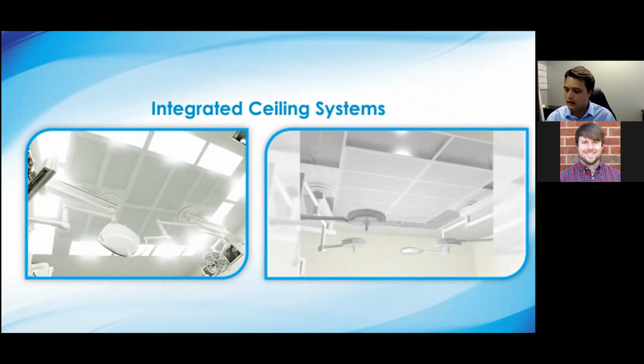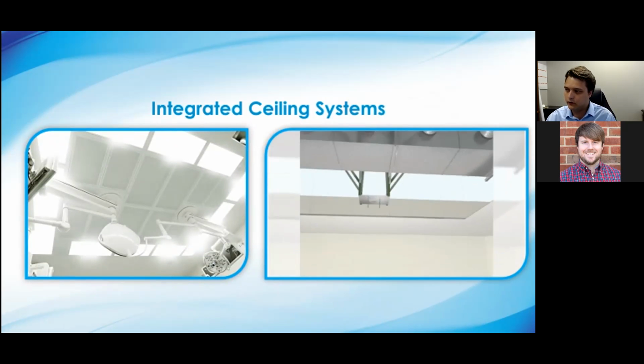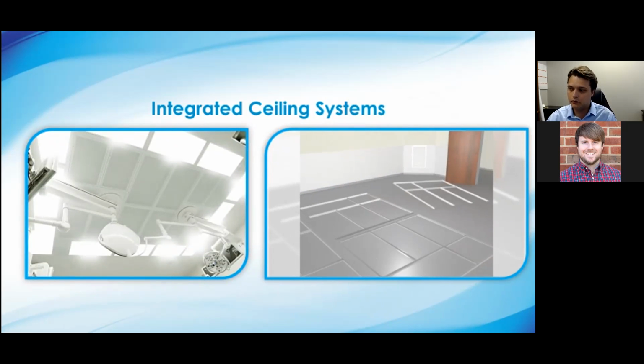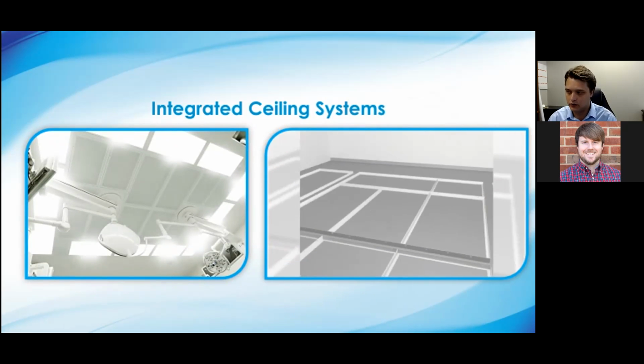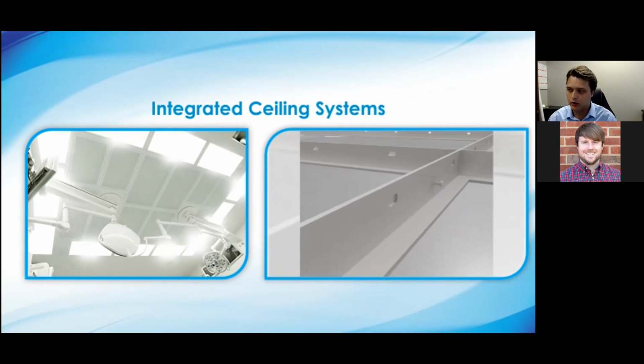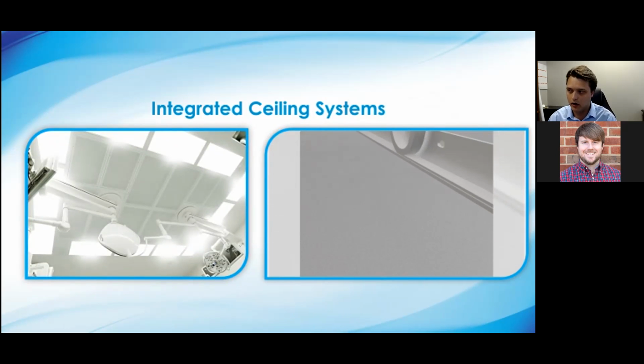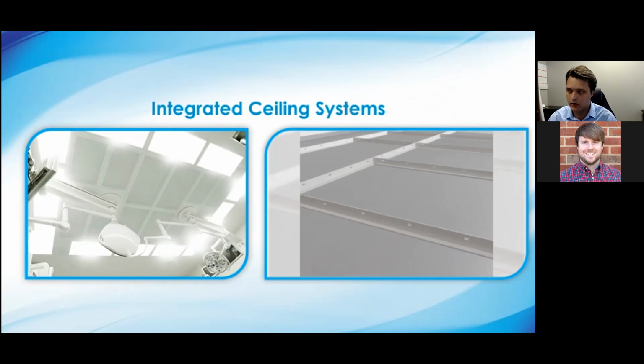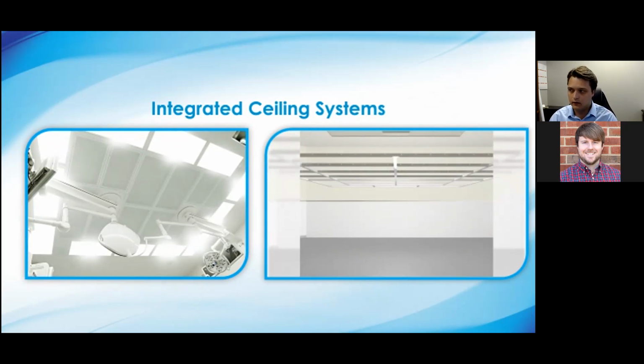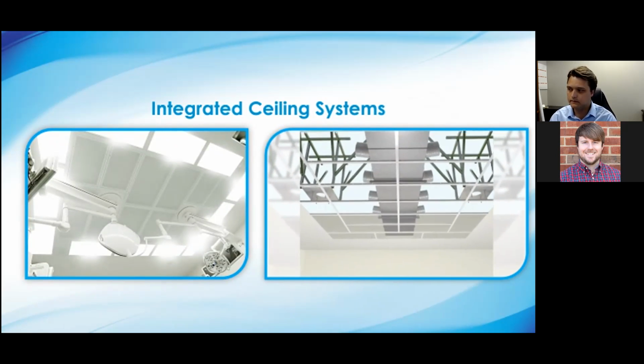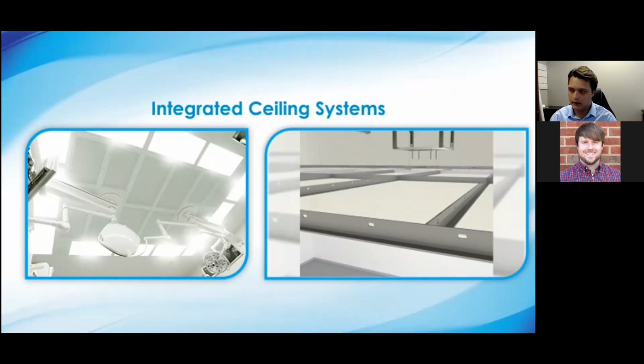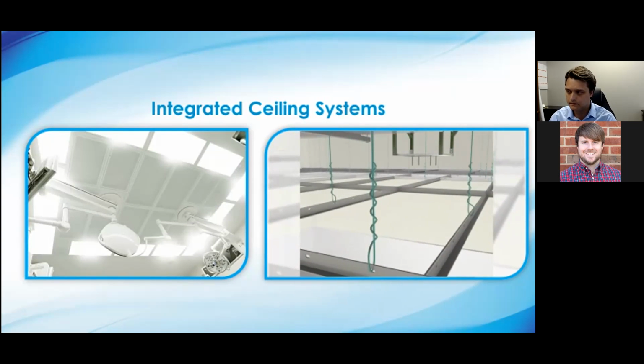Here we're going to look at an operating room under construction. We have one large ceiling opening. Those puzzle pieces, the modular framing sections, are prefabricated and pre-coordinated with all the openings and where everything is going to be within it. It's gasketed, fastened together, lifted up into the ceiling, and hung typically by just hanger wire or gripple.